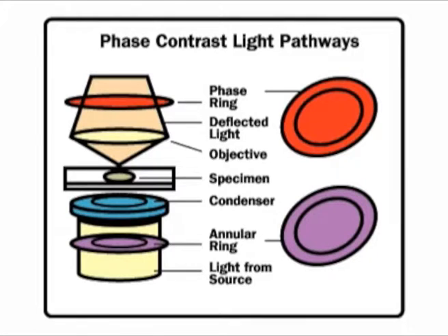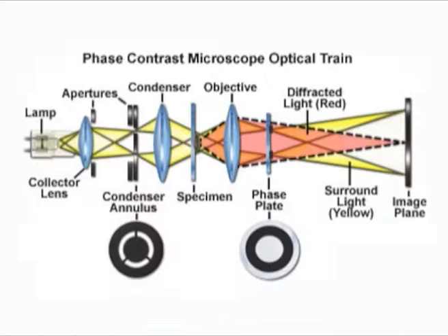This technique is based on the fact that the rate at which light travels through objects is inversely related to their refractive indices. This difference in phase due to changes in refractive index of the different components of the specimen imparts contrast to the images formed, making structures clearly visible. This microscope consists of a system of rings in the condenser and the objective.